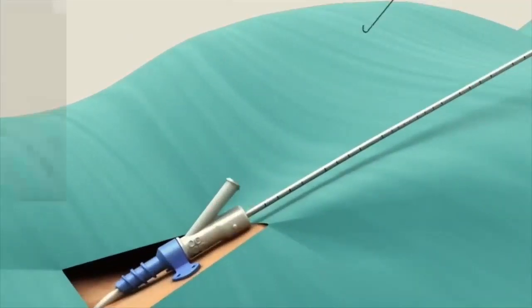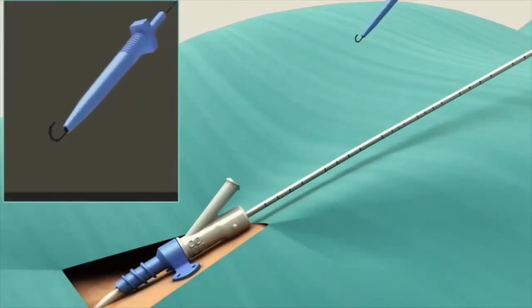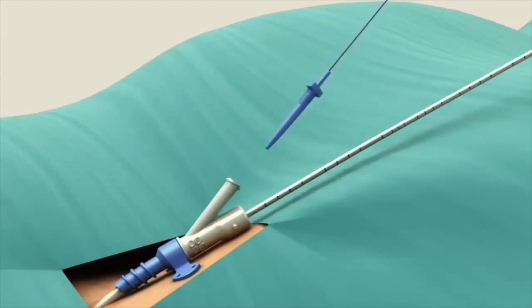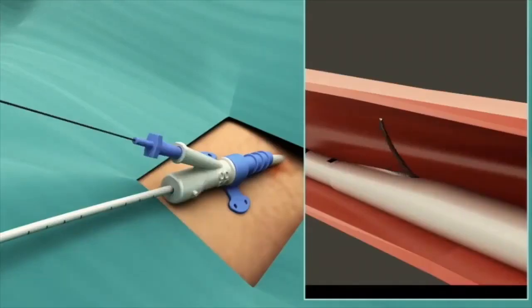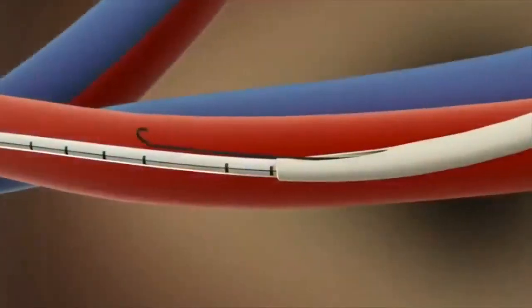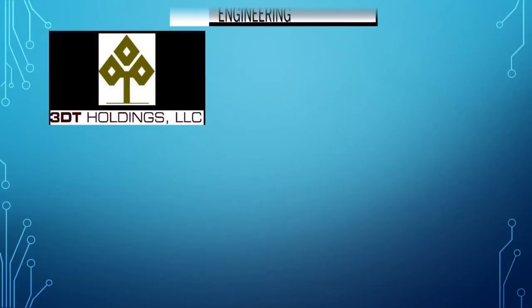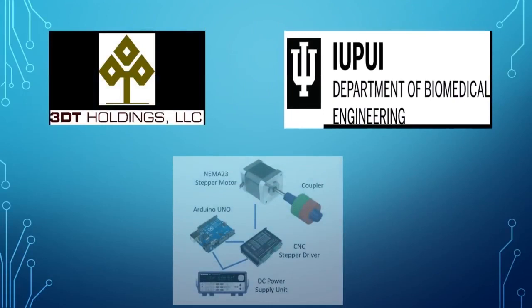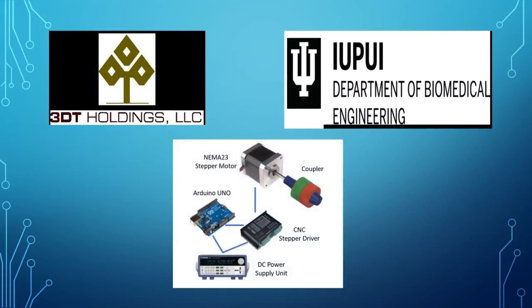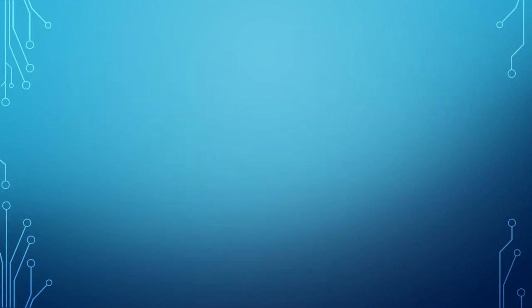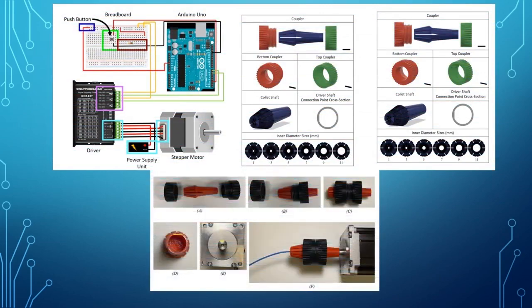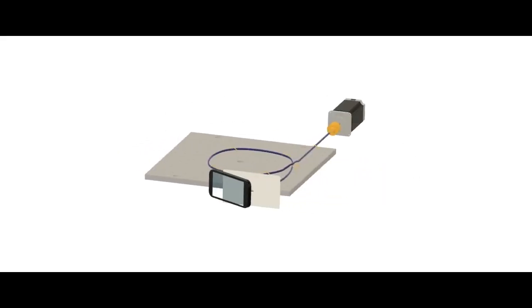Prior to approval by the FDA, guidewires and catheters undergo scores of testing to verify and validate the device meets regulations. For companies such as 3DT Holdings, LLC, thousands of dollars are spent during the design process by outsourcing testing to third-party companies. However, through partnership with 3DT Holdings and the IUPUI Biomedical Engineering Department, this student design team designed, verified, and partially validated a torqueability measurement system that is inexpensive, adjustable for various guidewires and catheters, simulates anatomical pathways, and supports a predicate equivalency argument.